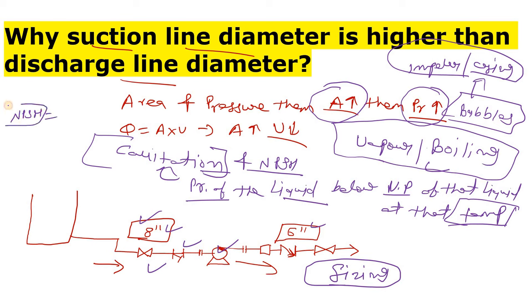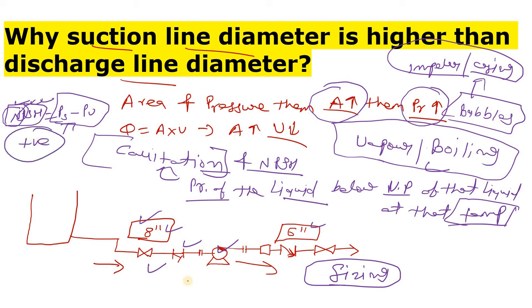If we know about NPSH - Net Positive Suction Head - it means the net suction head should always be positive. Your suction side pressure minus vapor pressure gives you the NPSH value. This difference should always be positive. If it is positive, your fluid is okay and your pump will run smoothly. But if it is negative, cavitation could occur.